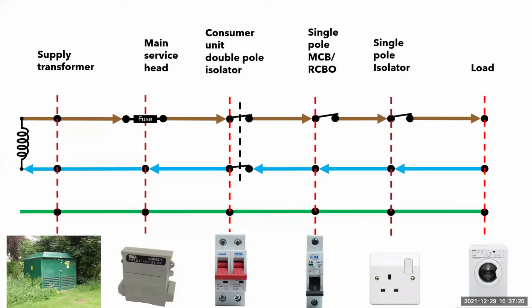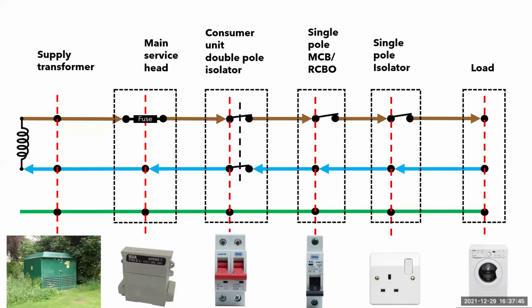In order to be able to work on the washing machine for mechanical and electrical maintenance, you need to be able to disconnect the appliance from the supply to prevent accidental energizing. Ideally, this isolation should be local to the appliance to enable low-skilled or non-electrical workers to work safely. If I then add in the enclosures for each point, we can start to look at the supply and load side of each point of isolation. Hopefully, once you start to understand this, it will make safe isolation easier for you to understand and the reasons why you isolate upstream when gaining entry to an enclosure.